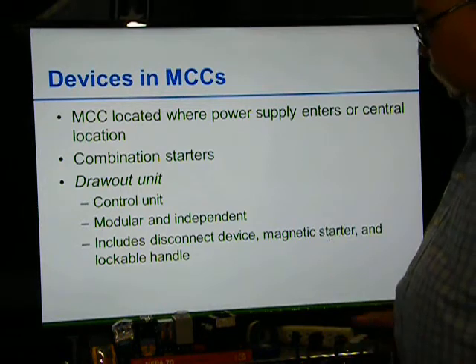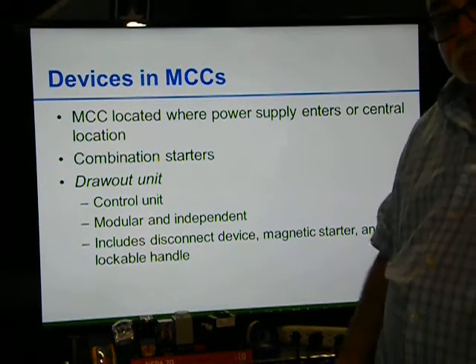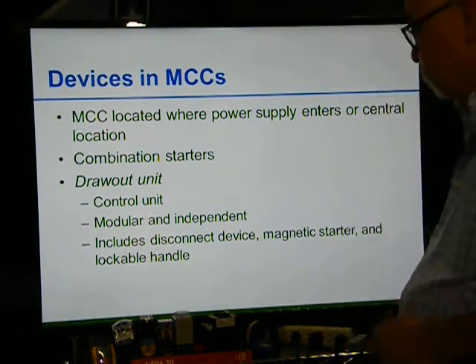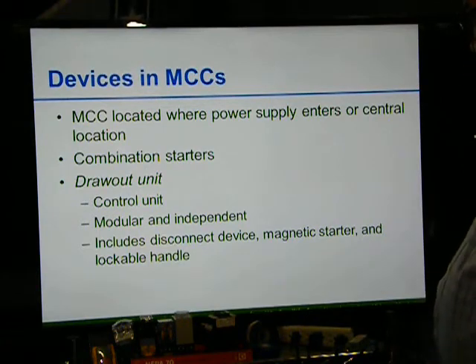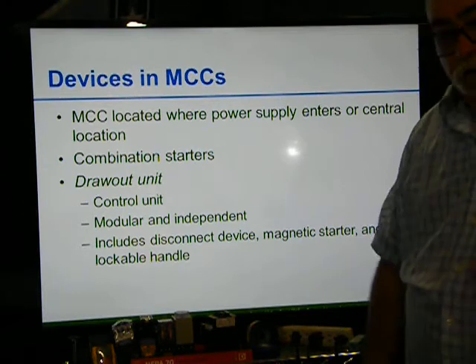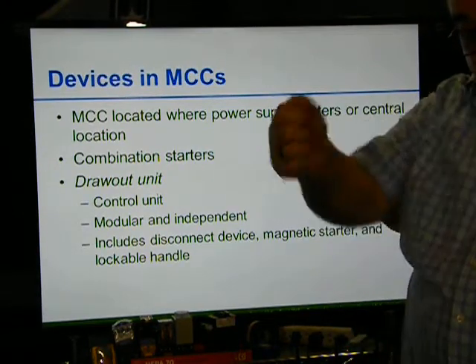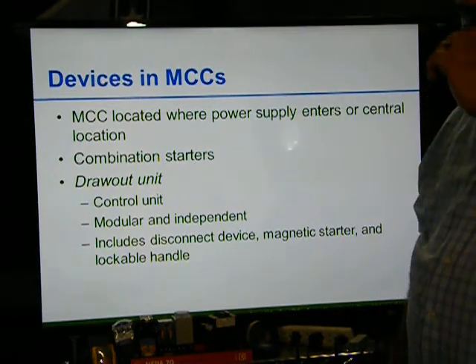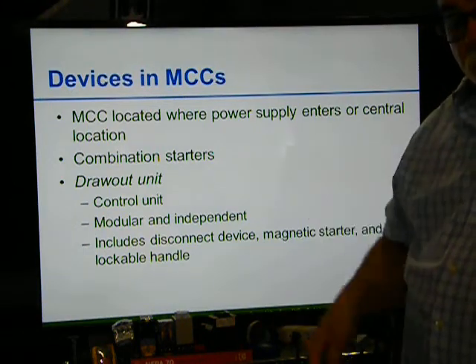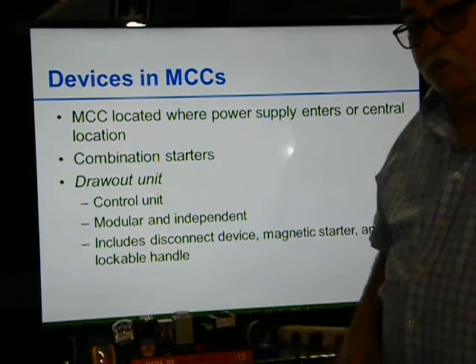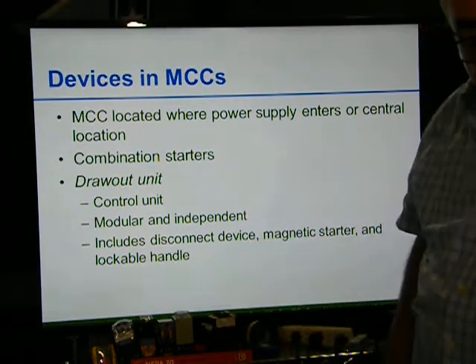So you have the control unit, the module. Each one is independent. We call them buckets. So one of the little terms is a bucket. It includes a disconnect device, magnetic starter, and a lockable handle. The breaker that turns it on and off is usually what holds the door down. It has a screw, but you can turn it on and off. You can turn each one off independently from all the other ones.